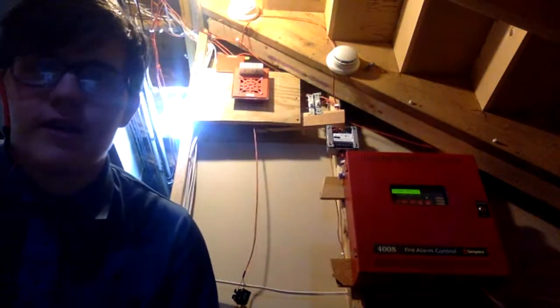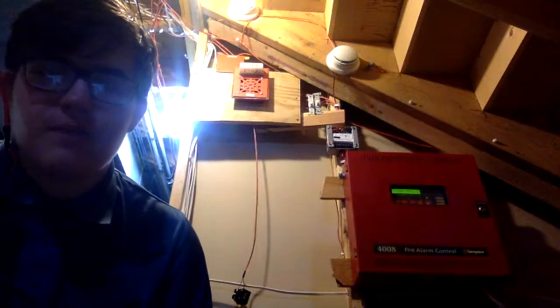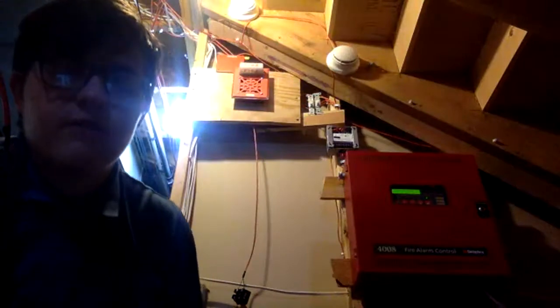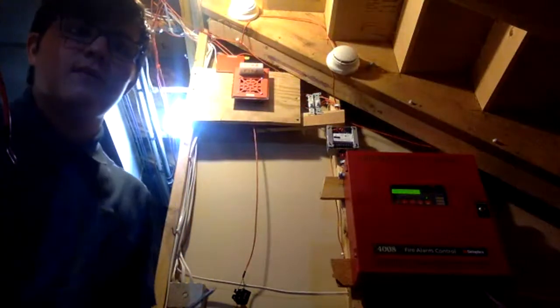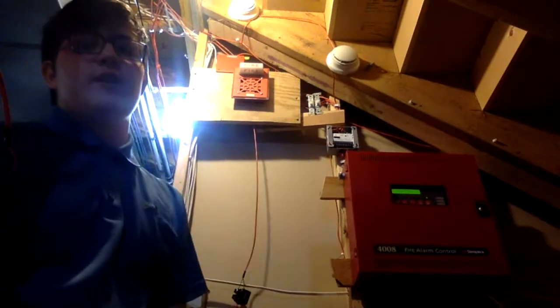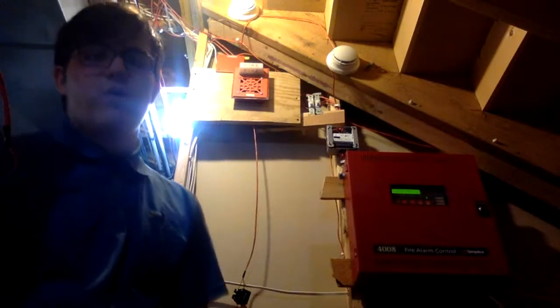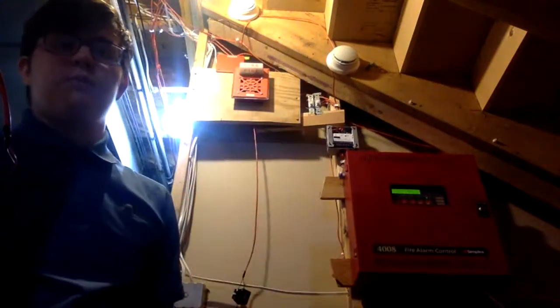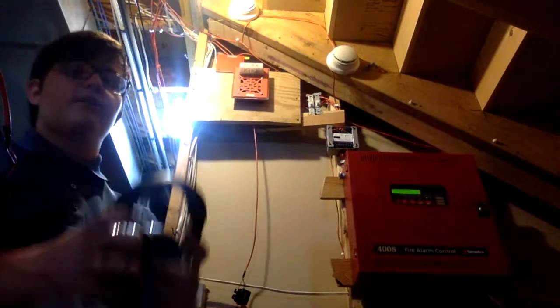All right. So it's not installed the best, but why doesn't the panel go into trouble when I take the alarm down? Because for the demo system, the resistors are in the panel, because I don't want to have to deal with the trouble every time I change that out. On the home system, the resistor's on the True Alert in the hallway upstairs, because that's the last device, but not for the demo. So the 7001T will be in code 3, but it'll get the point across.